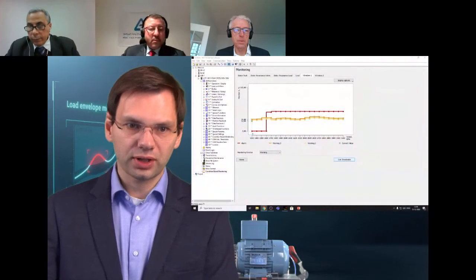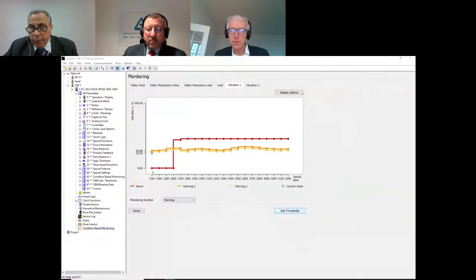Well, first of all, the monitoring we do is relative to speed. So you can see in this graph here, the vibration level is shown relative to speed. If in the application the speed itself would vary, then you would detect it as a change in the torque, because the drive sets the speed of the motor. And if the speed of the motor is not the same as the set speed, that means the load influences the motor, and that would then be seen as a load change. But all parameters shown here are shown relative to speed.